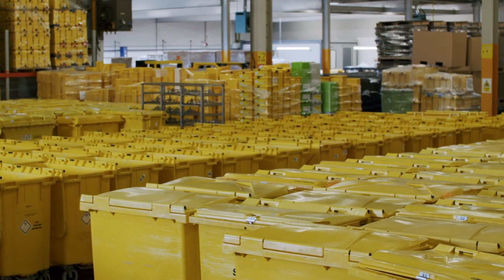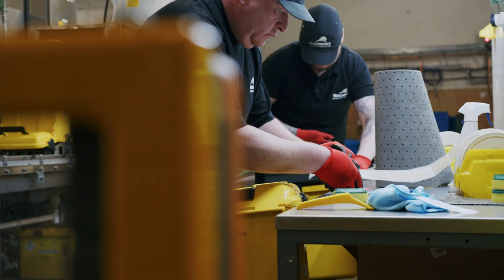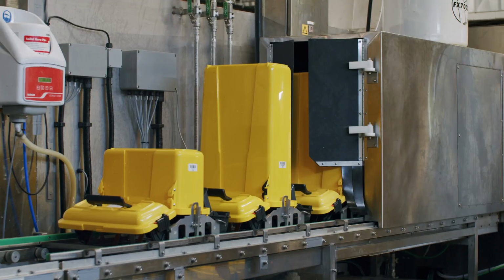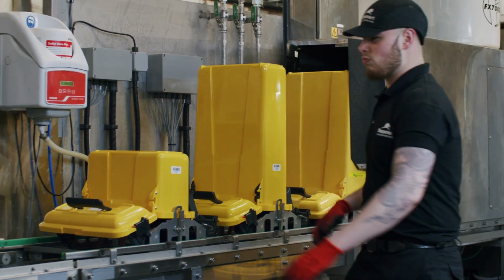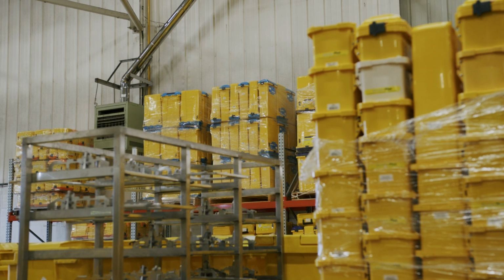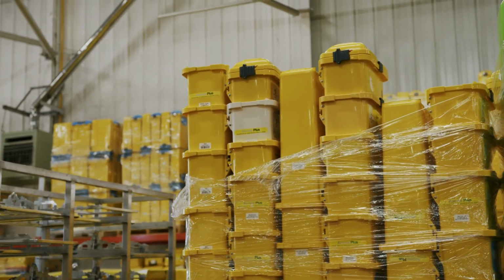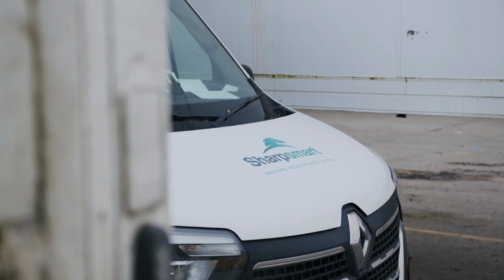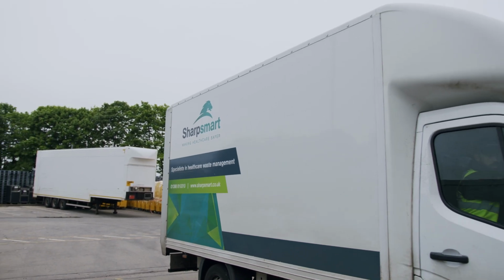I've swabbed many reusable Sharps containers, or as a matter of fact, single use as well, and their level of microbial contamination is very low. When they come from the hospital full, they have to be emptied, and then they have to be cleaned thoroughly. Now we said, okay, let's assume it's 4 logs. At the moment, the ISO Sharps container standard 23907 Part 2, the newly published Australian standard and the recently published Canadian standard all require that a reusable Sharps container be validated to remove 4 logs of pathogens that have been not just put on the surface in any fluid, but put on in whole blood and dried on the surface, which makes it harder to get off.